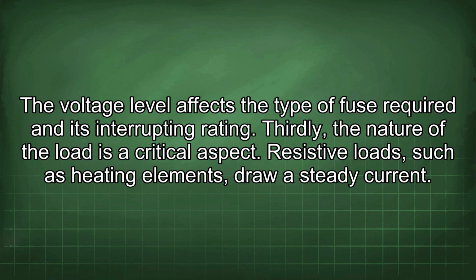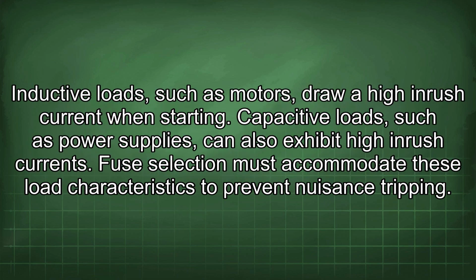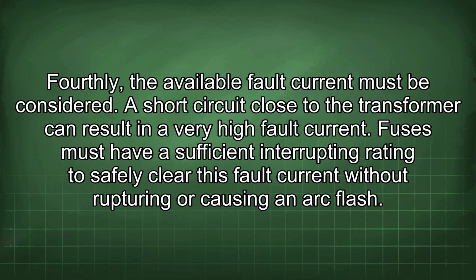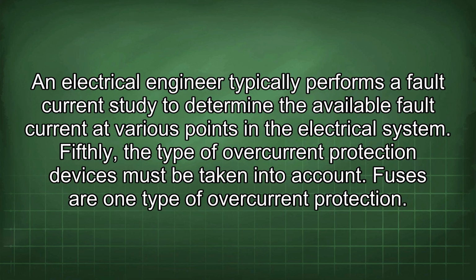Thirdly, the nature of the load is a critical aspect. Resistive loads, such as heating elements, draw a steady current. Inductive loads, such as motors, draw a high inrush current when starting. Capacitive loads, such as power supplies, can also exhibit high inrush currents. Fuse selection must accommodate these load characteristics to prevent nuisance tripping. Fourthly, the available fault current must be considered. A short circuit close to the transformer can result in a very high fault current. Fuses must have a sufficient interrupting rating to safely clear this fault current without rupturing or causing an arc flash. An electrical engineer typically performs a fault current study to determine the available fault current at various points in the electrical system.